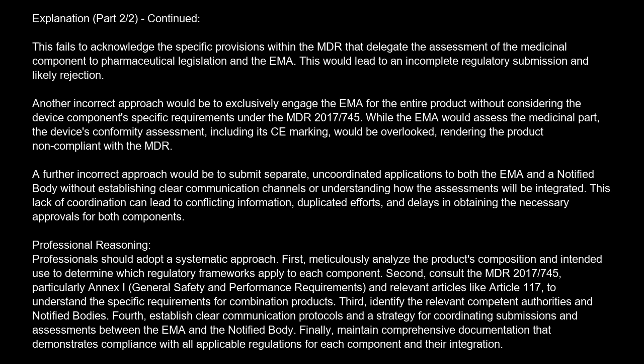First, meticulously analyze the product's composition and intended use to determine which regulatory frameworks apply to each component. Second, consult the MDR 2017/745, particularly Annex I, General Safety and Performance Requirements, and relevant articles like Article 117. Understand the specific requirements for combination products. Third, identify the relevant competent authorities and notified bodies. Fourth, establish clear communication protocols and a strategy for coordinating submissions and assessments between the EMA and the notified body. Finally, maintain comprehensive documentation that demonstrates compliance with all applicable regulations for each component and their integration.